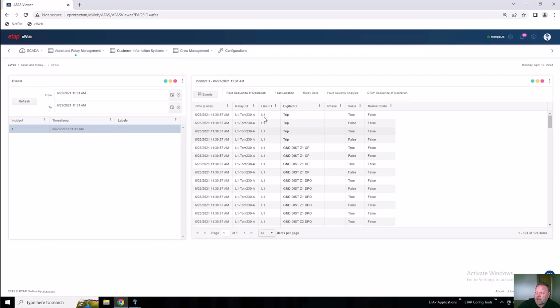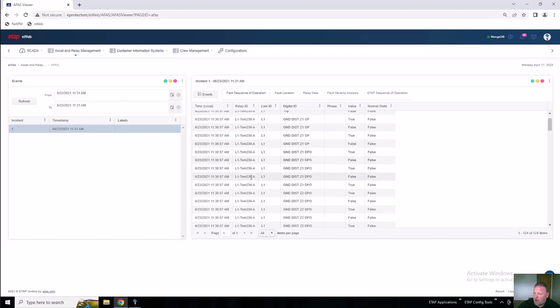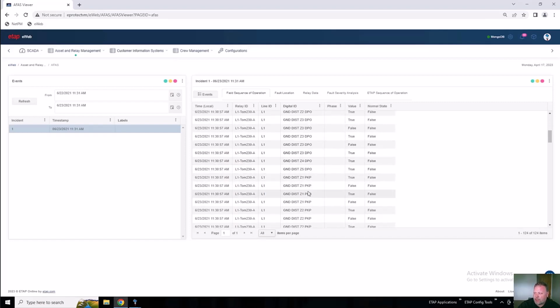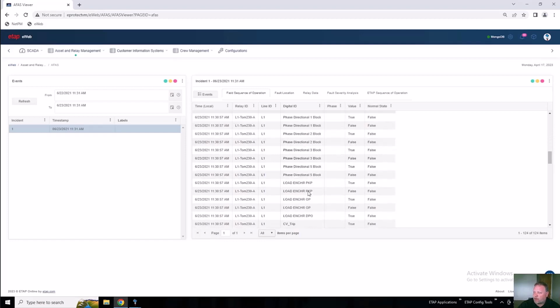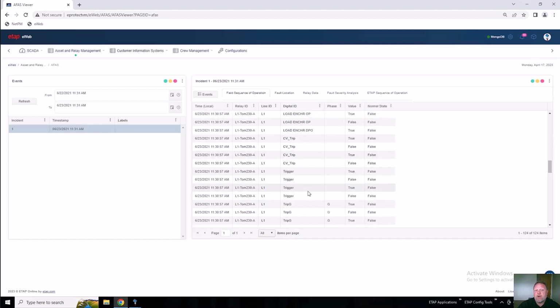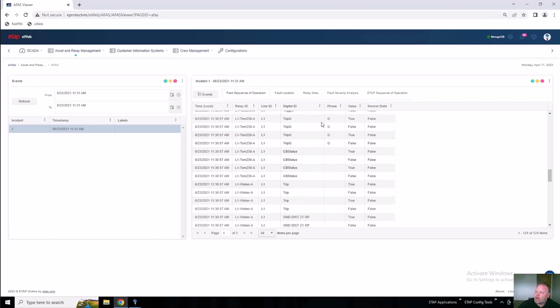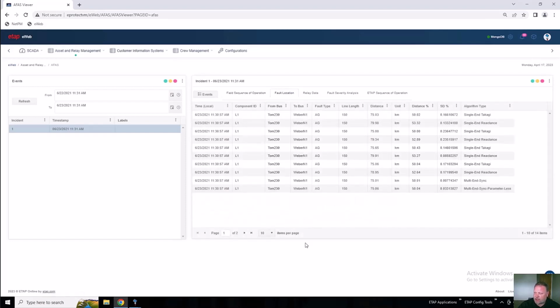You can see here also that this specific incident is a reclose operation because it went to true, then to false, then to true, then to false. So the initial condition was true, but then it tripped, and then it reclosed, and then it tripped again. Here you can see there are many other signals that we can bring in from the disturbance record. So this is the raw data from the disturbance record from the relay. Now I can go into the fault location section.